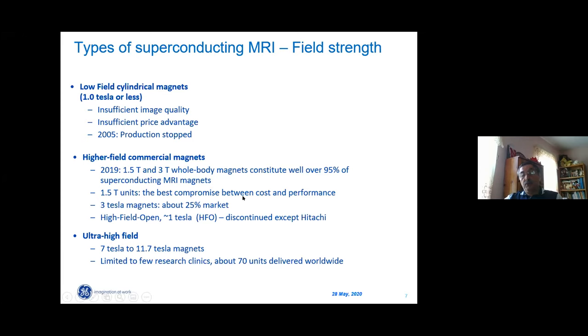Just one number published by Harvard Medical School: a typical 1.5 Tesla scanner, not magnet, installed is $800,000. If you say, look, we need to build an MRI magnet, it will cost well over $800,000. At some time we had an idea about so-called open configurations. We will discuss them later, but they're practically discontinued. There is a relatively small fraction of ultra high field scanners, 7 Tesla to 11.7 Tesla magnets, but these are limited to research clinics. Only about 70 to 80 units delivered worldwide.